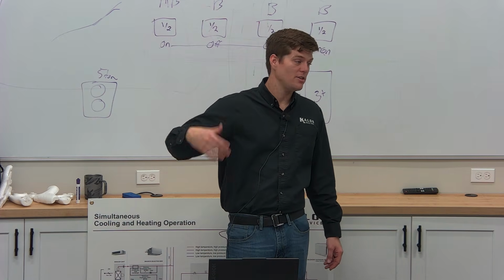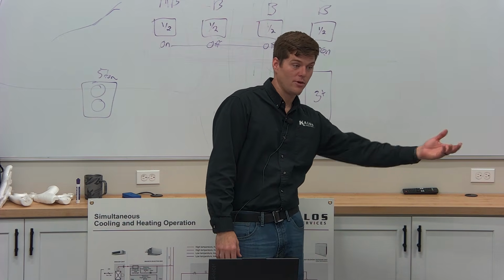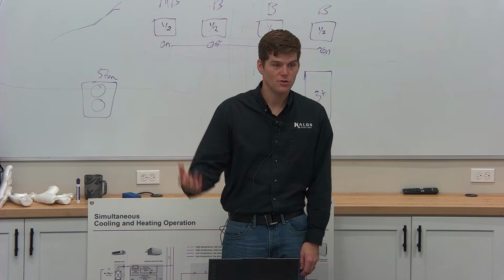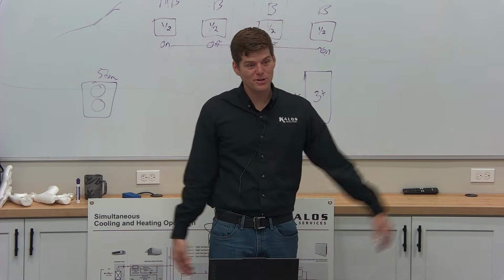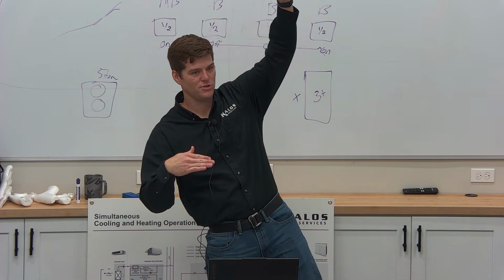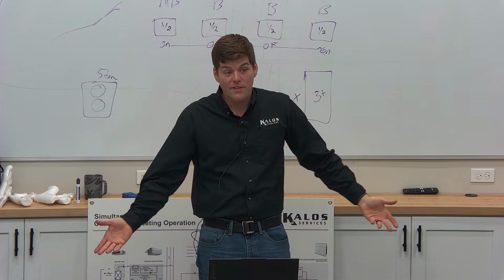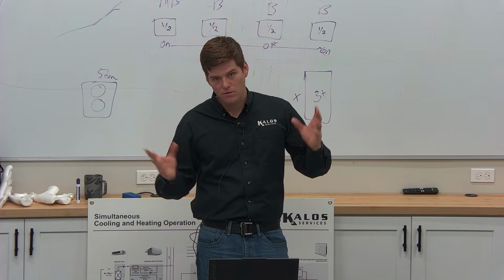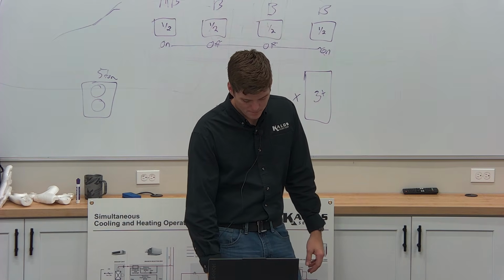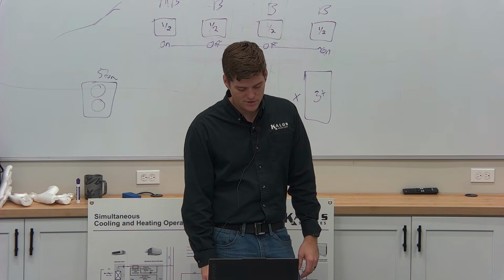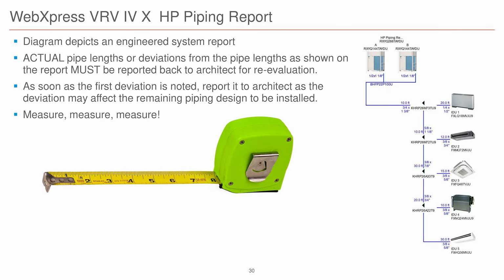You multiply that by so many units, and now your outdoor compressor is chugging liquid. Scrubs all the oil out of the compressor. Compressor still thinks it's got this much oil when really it's got this much oil. And that's what happens. That's the story that's on repeat all over the U.S. that kills this equipment, that gives it a bad name. That's an installation deficiency.